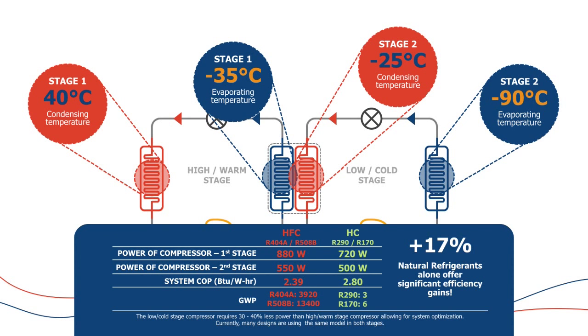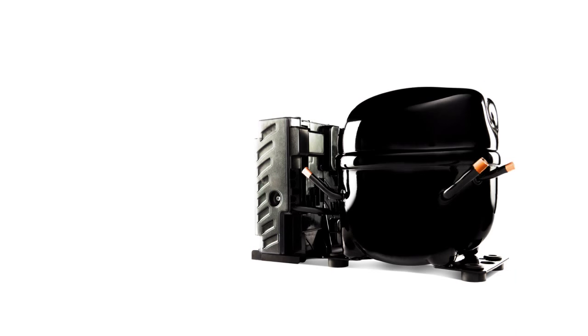One thing to consider: the lower second stage is typically going to need about 30% to 40% less power from the motor compared to what the high stage needs. But currently, most systems are using the same compressor on both the high and the low stage. So how do we solve this problem?